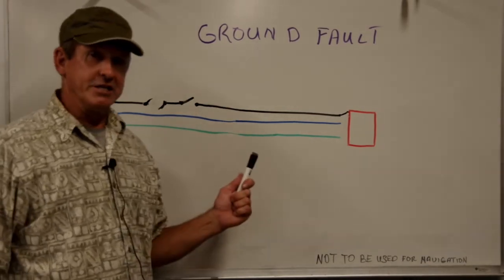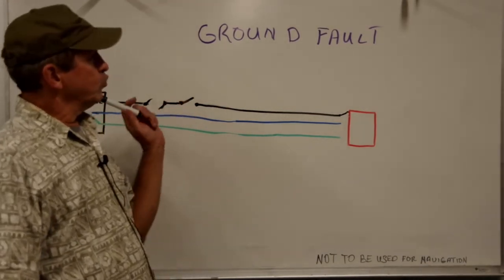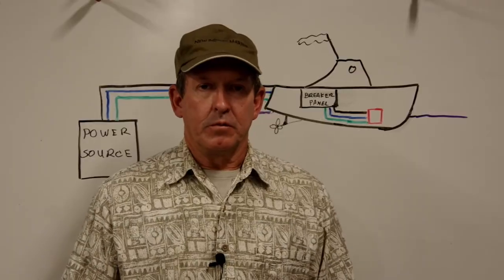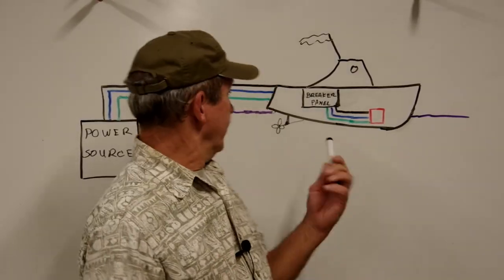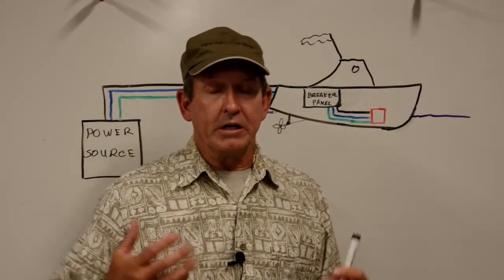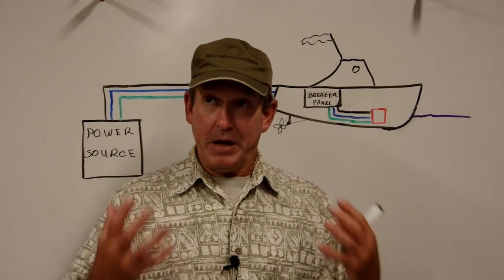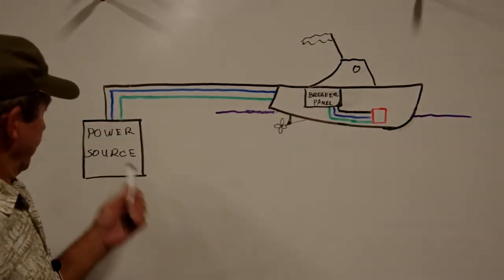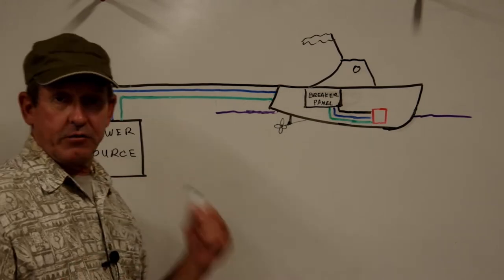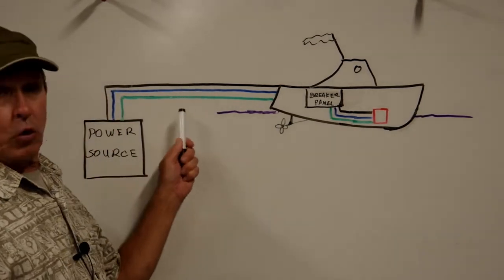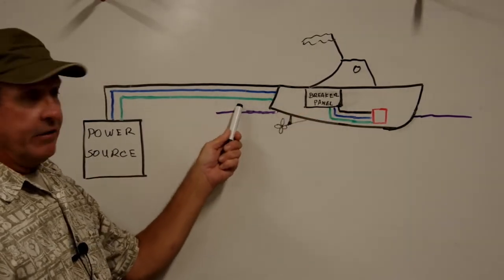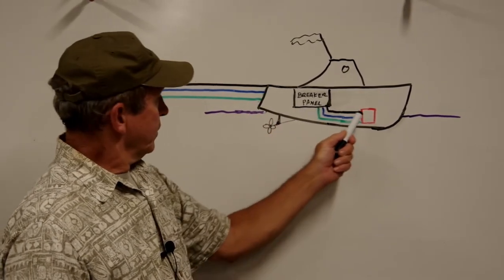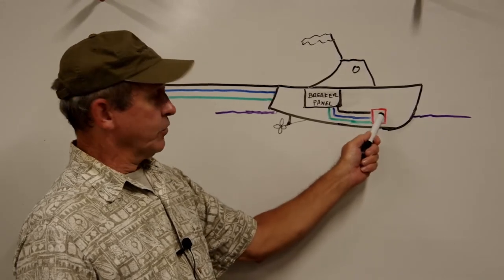Give me a minute to clean the board — I'm going to draw in a boat with a ground fault and show you why that is such a big deal. In our example, we have our source of power — more than likely the big transformer in the marina. We've got our shore cord plugged into our boat with line, neutral, and AC safety ground — our 30-amp shore cord. That goes into our boat, our breaker panel, and we have a circuit with line, neutral, and AC safety ground going to our appliance.